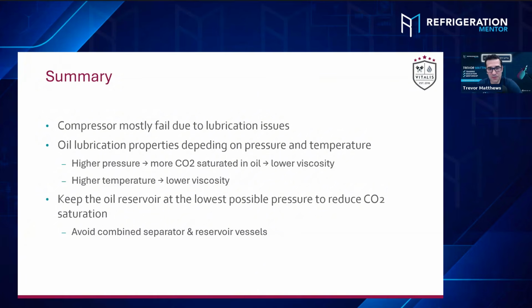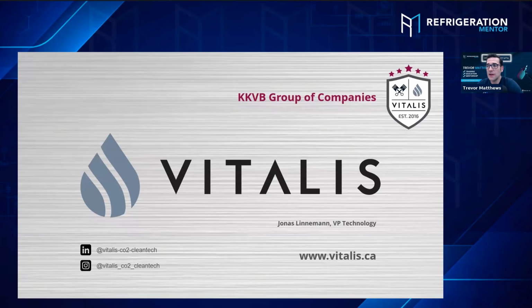Awesome. Jonas, this was amazing. I learned a ton. We have quite a few questions, and we answered a few of them, but I think it'll be good for a review. The impact of too much oil in the secondary circuit. Well, like Jonas says, if there's too much oil out in the system, it's not at the compressors. So that's the impact. You're going to trip off on your oil level control. You're going to trip off on your oil reservoir or your compressor itself because the oil is out in the system.